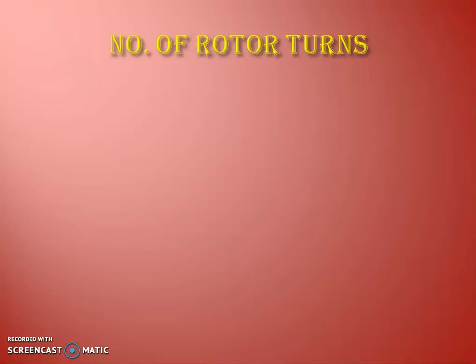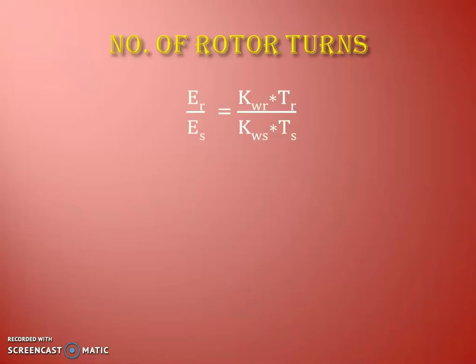Our next design step is number of rotor turns. The rotor represents the secondary of a transformer, and the voltage between slip rings is maximum when the rotor is at rest — that is the standstill condition. Therefore, to keep the rotor voltage to an acceptable level, we must effectively control the stator to rotor turns ratio, just like a transformer. The ratio of rotor voltage to stator phase voltage is purely dependent on the turns ratio of rotor to stator turns.